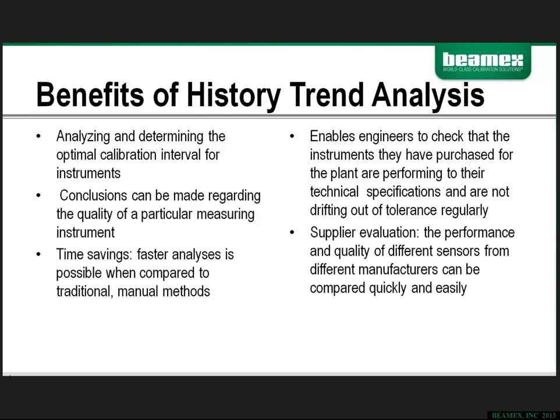And there are a lot of different manufacturers of sensors out there, and even one manufacturer may make 4 or 5 different temperature transmitters that would meet the particular criteria for what you're doing. If you could determine that over a period of time, one particular sensor performed well enough that you didn't have to perform calibration actions as often, it might be more financially reasonable to use that particular transmitter when other transmitters, based on age or life cycle, would need to be replaced. Because once again, it's going to save you time and money down the road, which in this day and age we're all trying to do.